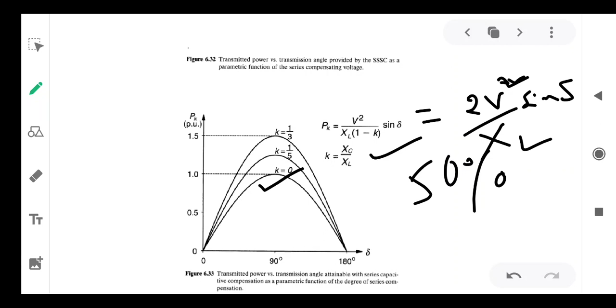Now let us compare the same thing with the SSC characteristics. These are the characteristics of SSC: without any compensation, with negative compensation, overcompensation or inductive compensation, here with compensation of 0.5. The operating point is increased from 0 to a higher value, and therefore the power angle curve is enhanced. The maximum power can be increased for the stability region. Similarly, as VQ increases, the maximum power point can also be enhanced with the help of SSC.